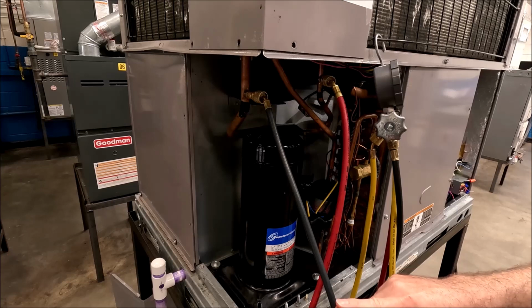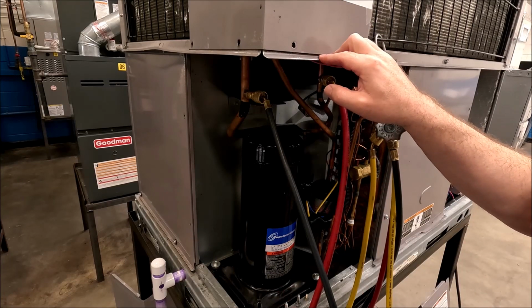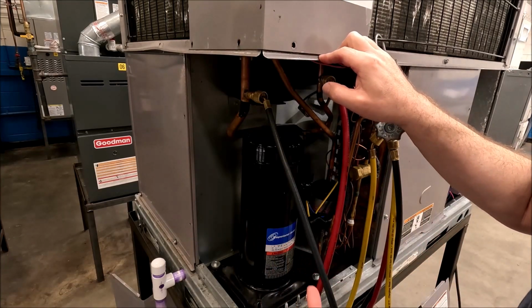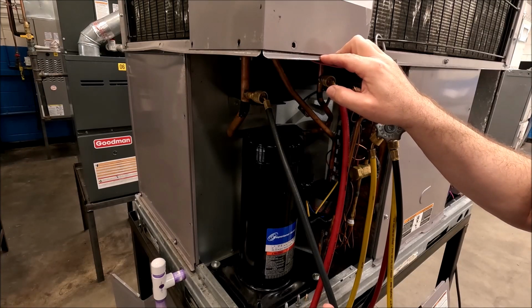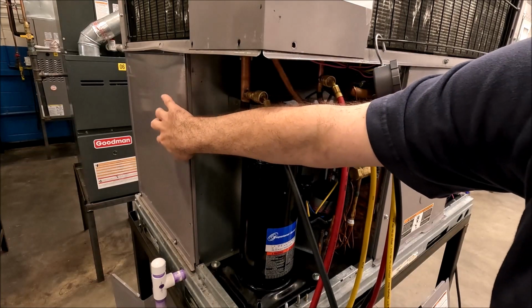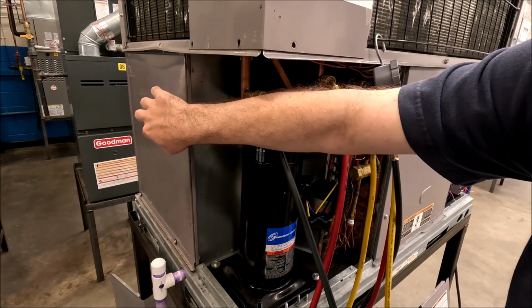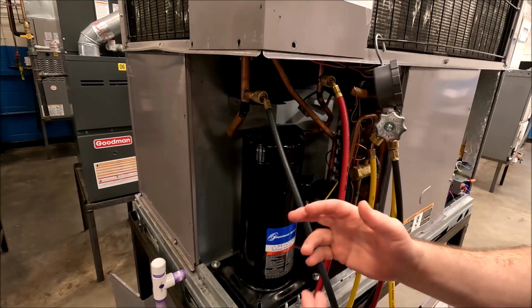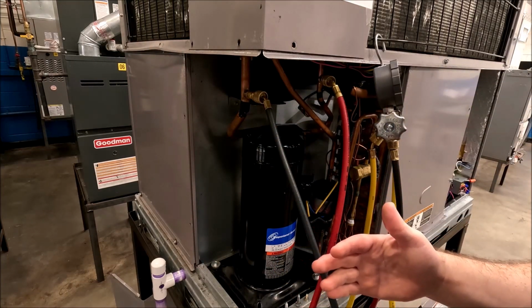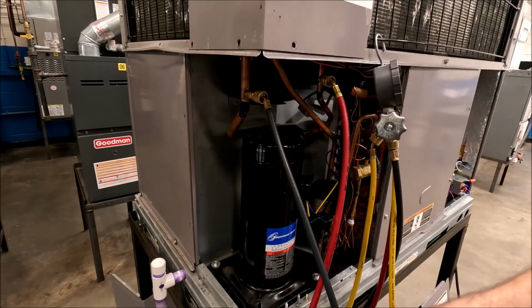So for what I'm going to do here, the best thing I can do is take a return temperature outside through this panel here. I'll show you that in just a second. And I'm also going to take a condenser coil temperature. I need to know the air temperatures entering both coils. So hang tight, I'm going to move over there and I'm going to show you what I would do.